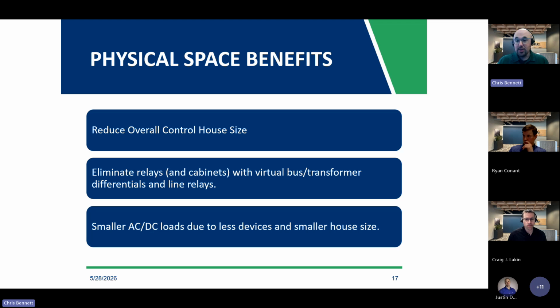So we heard about the physical space benefits early on, reducing the overall size and number of cabinets, but another benefit that is not immediately obvious is you will have smaller AC and DC loads due to fewer devices, and a smaller control house also needs fewer HVAC units, which can definitely drive up the cost of a project very quickly. If you are running specialized equipment inside the control house for a renewable project, such as a power plant controller or battery storage type controller, they usually have some kind of requirement for that.